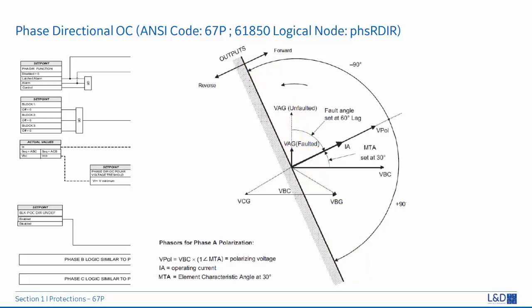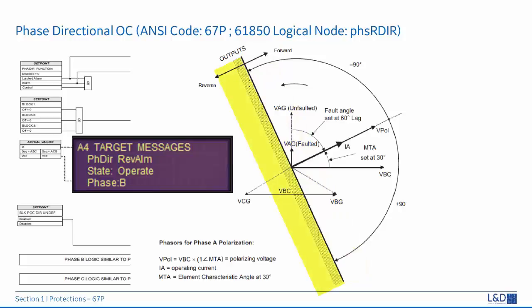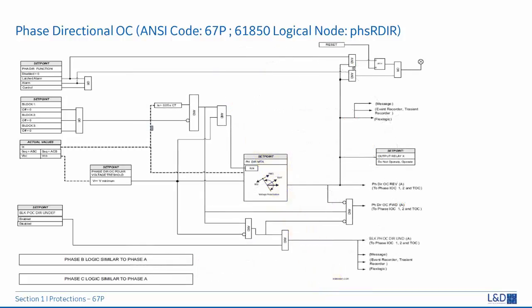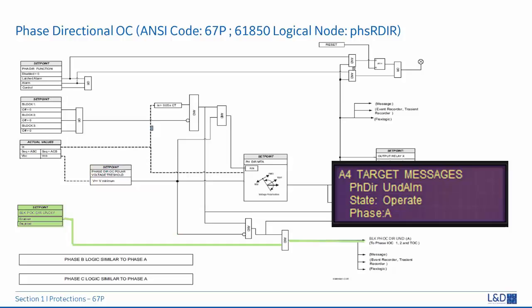When the operation comparator is based on operating current and polarizing line-to-line voltage and MTA, with MTA set to the default 30 degrees, the forward region for phase A current angle will be 330 degrees to 150 degrees lagging. The reverse direction will be 150 degrees to 330 degrees lagging. When phase directional block OC undefined is enabled and VT voltage is below minimum supervision level, the block phase OC directional undefined operand will be asserted.